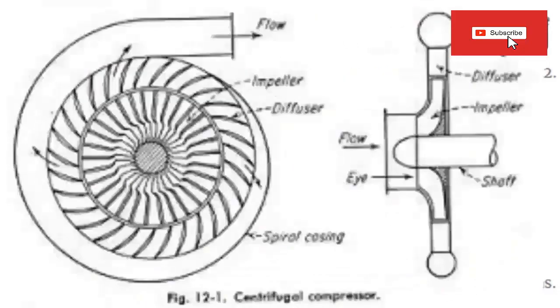12. Up to 11% more capacity, compared to R12 refrigerant gas. 13. Low compressor discharge temperature compared to R12. 14. Its use in centrifugal compressor systems is not recommended. 15. Not for use on flooded evaporators.